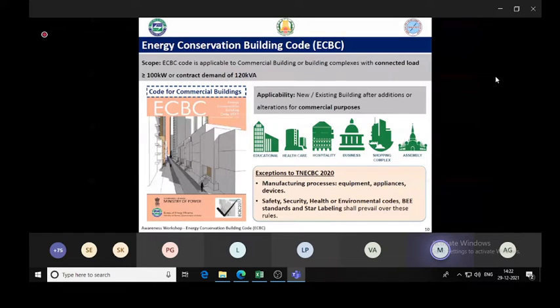When you construct a building, when you plan for a building, you need to estimate what your connected load is going to be. And if that is going to exceed 100 kilowatt, you need to apply for ECBC compliance. Once it is in force, even before you go for your plan approval, you need to comply with ECBC. When we talk about commercial buildings, it could be an office building, hospitality, a healthcare building, auditoriums, education institutions. Except manufacturing industries, all commercial buildings will be covered in the code.